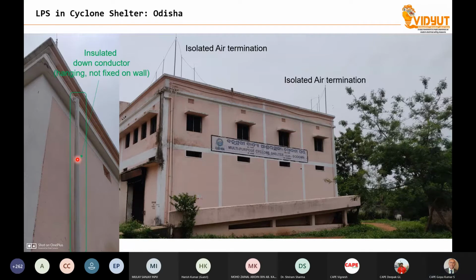It is an established fact that down conductors must be fixed to the building very strongly. You cannot hang it loose, because the mechanical forces created by the lightning are very, very heavy. If your fixing is not proper, it could create an explosion. So you are supposed to fix it very firmly, whereas this down conductor is hanging through a pipe. Next, the down conductor is very expensive, 3,500 rupees per meter. This conductor is hanging through the pipe, and it is hanging on the side of the building.